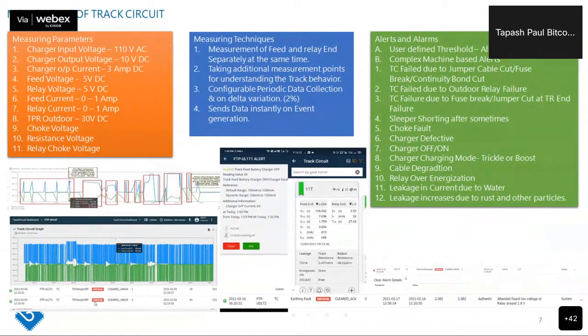Take the example of TPR outdoor and TPR indoor. Suppose the TPR cable goes from indoor to outdoor, is 1 kilometer in length, and returns from outdoor to indoor. Outdoors I am getting 30 volts, and indoors it is coming only 26 volts, and the gap is gradually increasing. So we can tell that over the 1 kilometer cable there is a loss of 4 volts. If it is gradually increasing, we can tell that the cable insulation or some other factor is affecting the cable health, so the cable is degrading. This type of alarm we generate with this data.